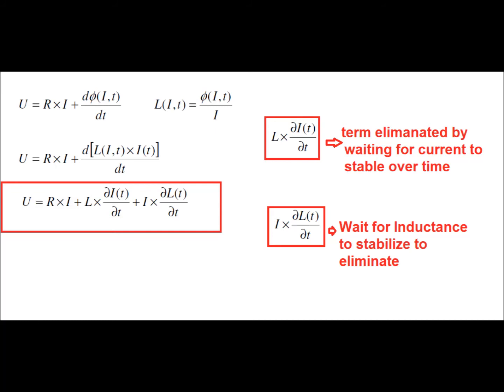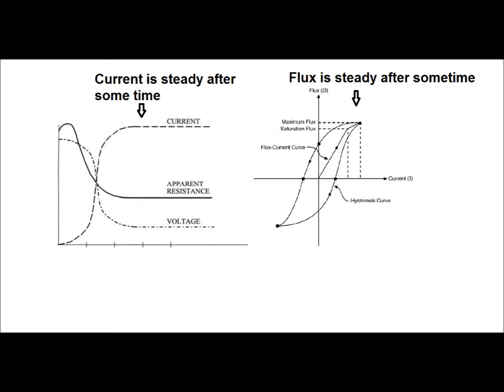Our motive is to calculate only R into I and to eliminate the second and third terms. The second term is eliminated by waiting for the current to stabilize over a certain time, which normally takes a few seconds. The third term is eliminated after the flux gets saturated, or reaches a fixed point, after some time. In this diagram, it is shown that the current is steady after some time, and therefore the apparent resistance can be measured when the current is steady and the flux is steady as per the BH curve shown in this diagram.